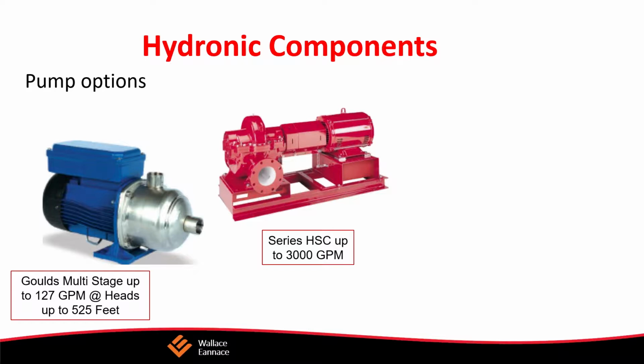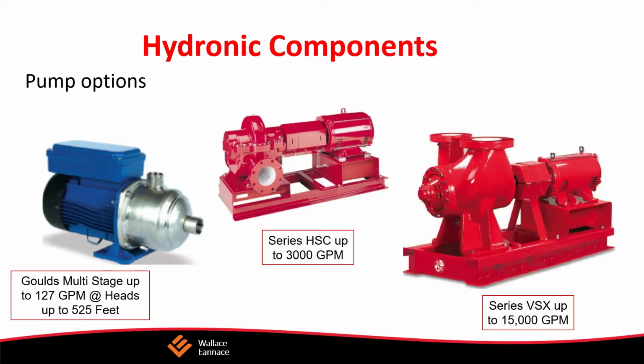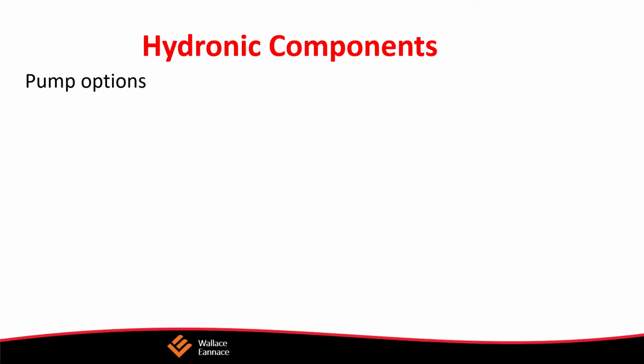Let's take a look at what kinds of pumps we have. We have oil. A lot of the old pumps were oil lubricated pumps. Those are like the Series 100 and the HV pump. Their components were simply a motor, a coupling, bearings, shaft, seal, and an impeller in the loop. These oil lubricated pumps have been around a long time. They're sort of last year's technology. A lot of people still put them in, in retrofit situations, because they know they're going to fit, they know they work. But in many cases, that oil lubricated pump can be replaced by a permanently lubricated pump.